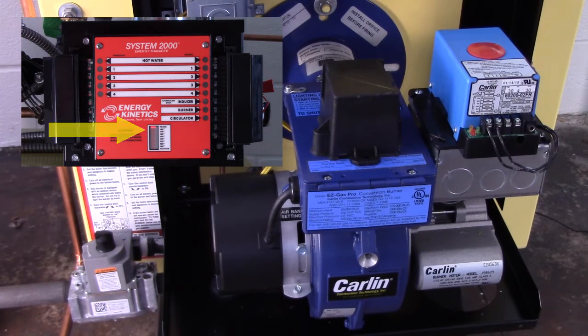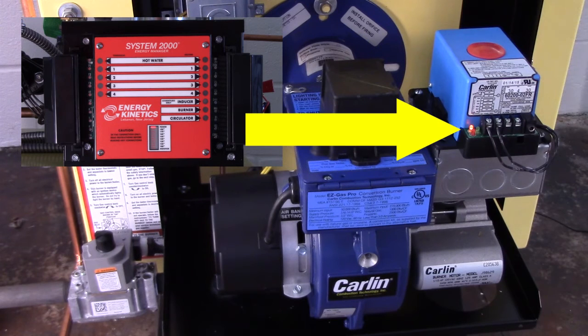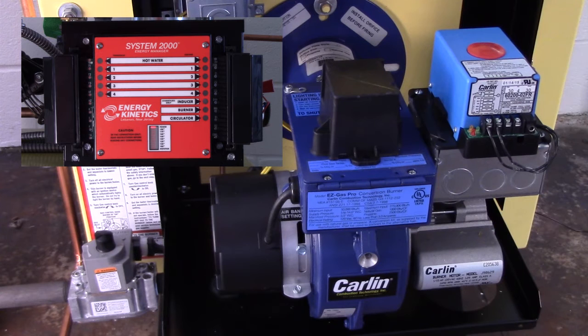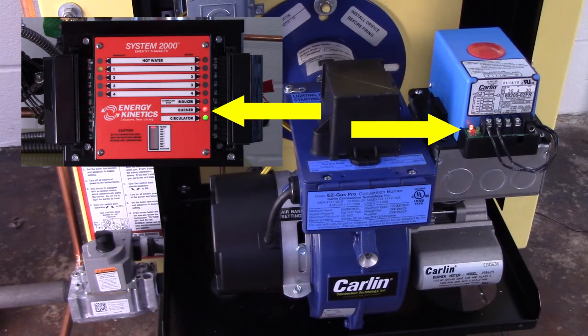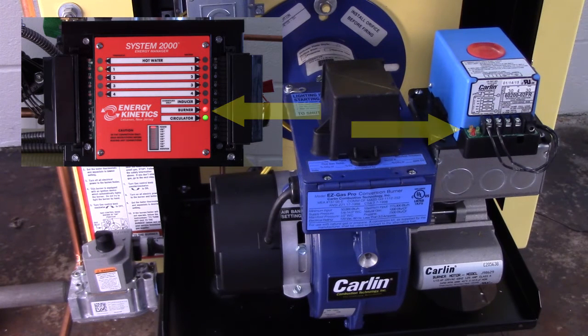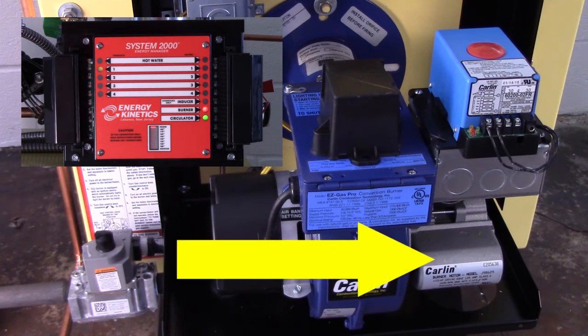About 4 seconds after power is applied, the amber LED turns on. The test continues for about 6 more seconds. The control enters standby mode if there is no call for heat. When the manager receives a call for heat or hot water, self-test 2 begins. The manager's burner light turns on, the amber LED turns on. The motor starts and pre-purge begins for about 30 seconds.